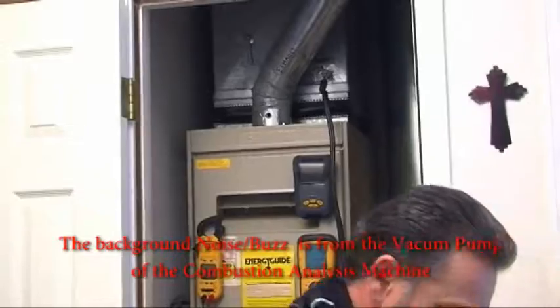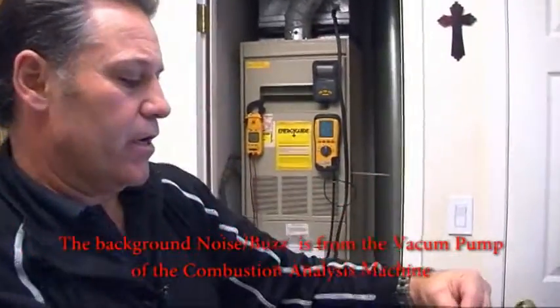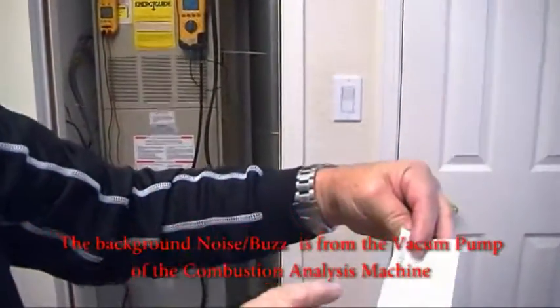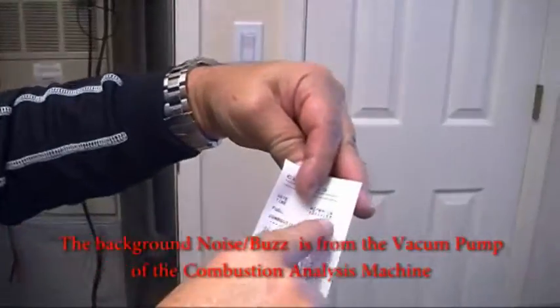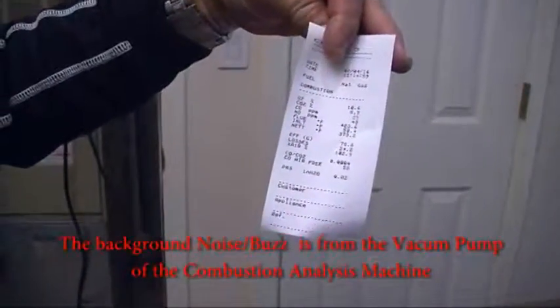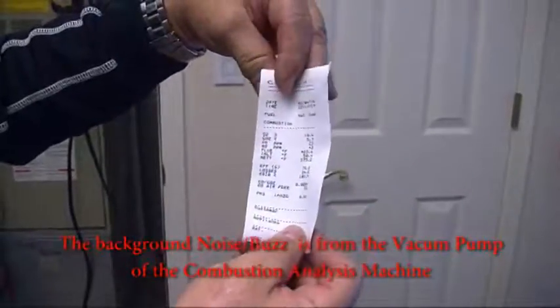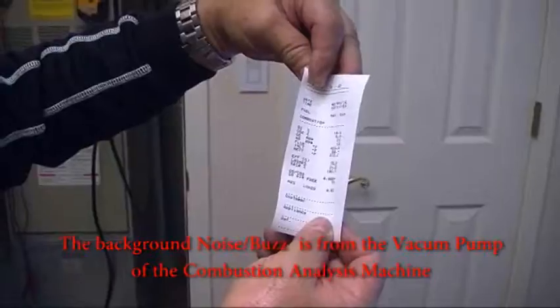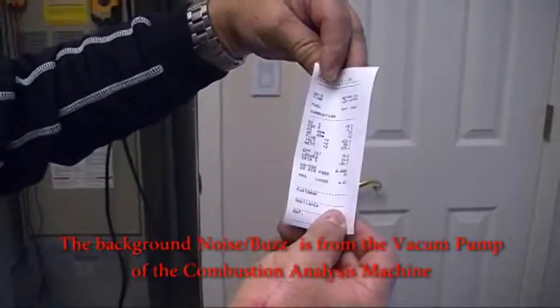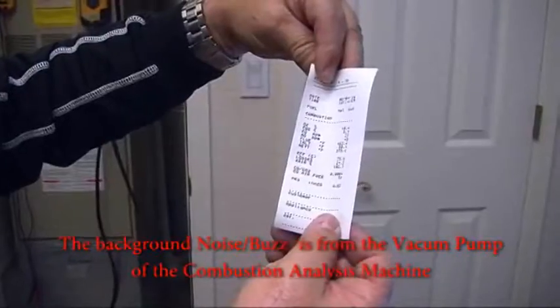Let that go. These are the results of the combustion analysis. This tells us that on February the 4th, 2016 at 12:14 p.m. with natural gas, our oxygen was at 10.6. Our carbon dioxide, which is our fuel, is 5.9. Our carbon monoxide is 29 parts per million. Our NOx are 43 parts per million, and our flue temperature was 423.6.